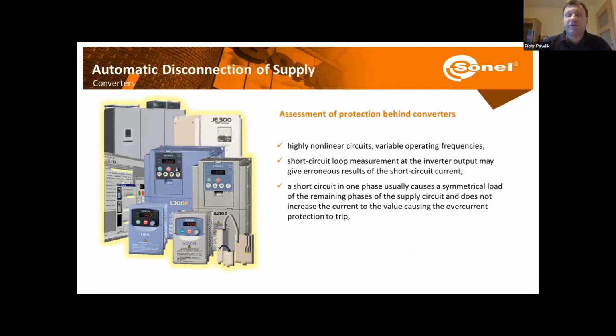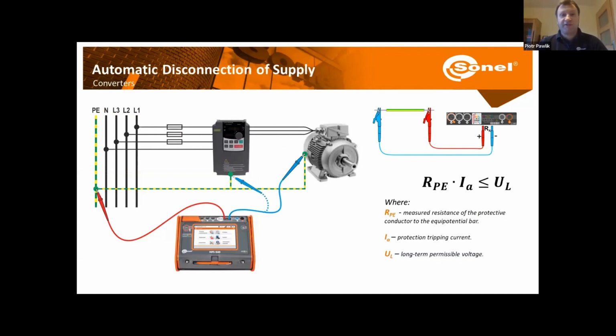Another situation is what in case we have some converters like rectifiers or inverters. What then? Can we measure fault loop impedance in that situation? Well, unfortunately, this is physically impossible, but in that situation, we are going to check the continuity of our protective channel. And then similar to the case of the RCD protection, we're going to take the resistance of the protective wire, multiply it by the tripping current of our protection, and this should be lower than the long-term permissible voltage, so lower than the 50 volts.